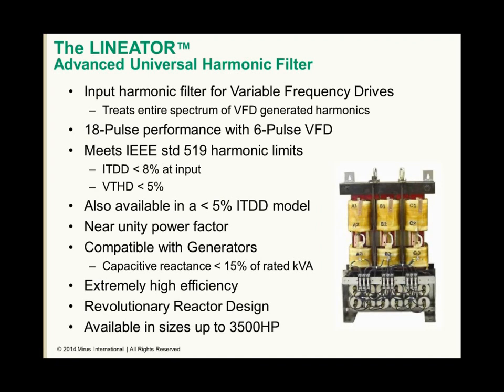Mirus offers a passive harmonic filter known as a Lineator, which is an input filter for variable speed drives and treats the entire spectrum of the harmonics generated by the VFDs. It will provide performance better than 18 pulse when applied to a 6 pulse VFD. We guarantee that IEEE 519 harmonic limits will be met, with current distortion less than 8% regardless of the short circuit ratio, and voltage distortion less than 5%.